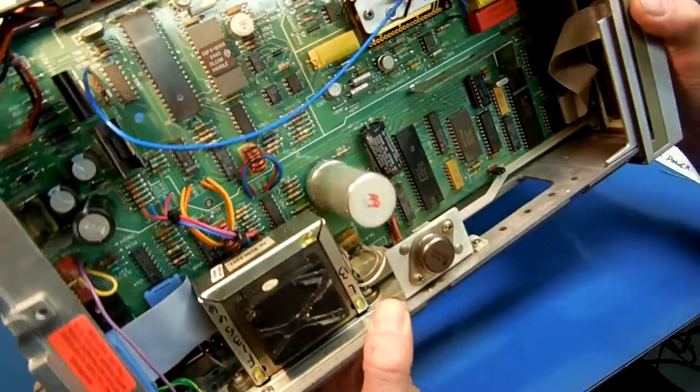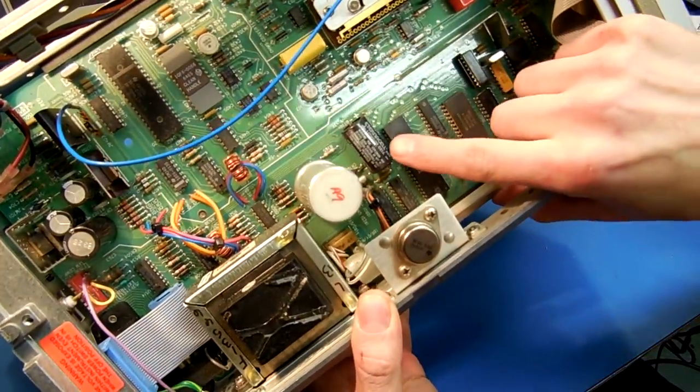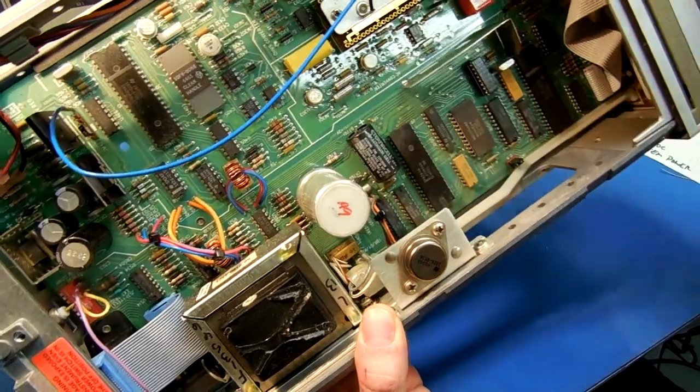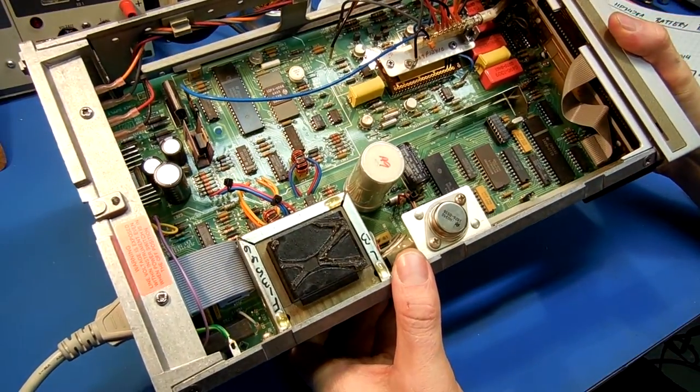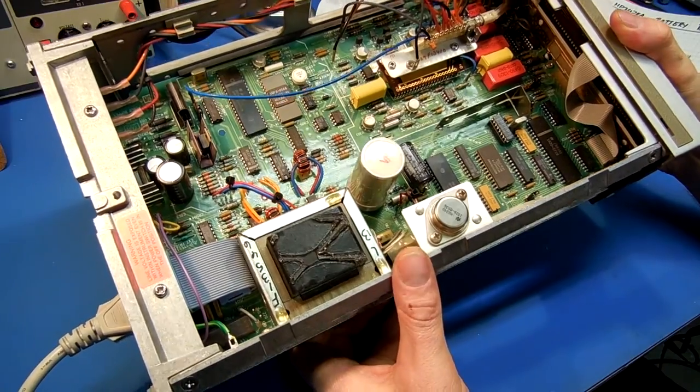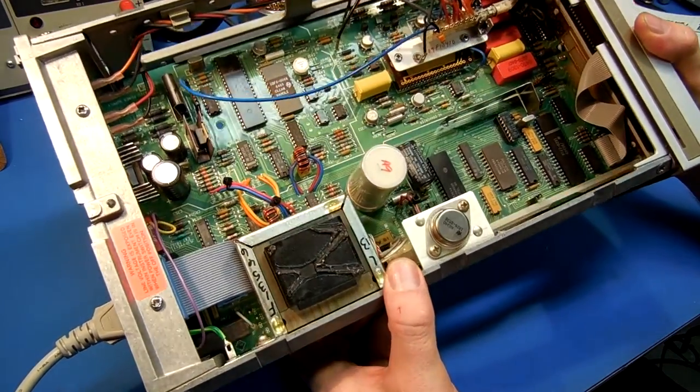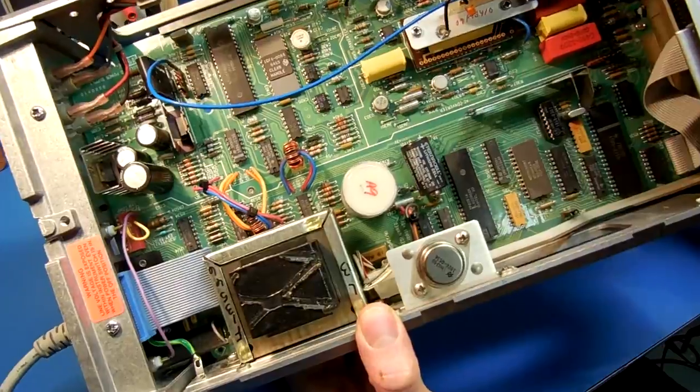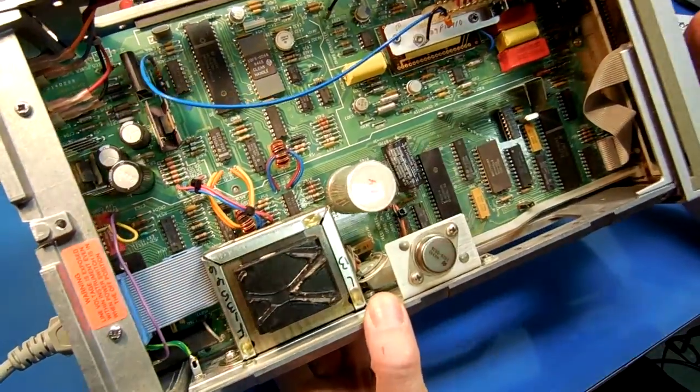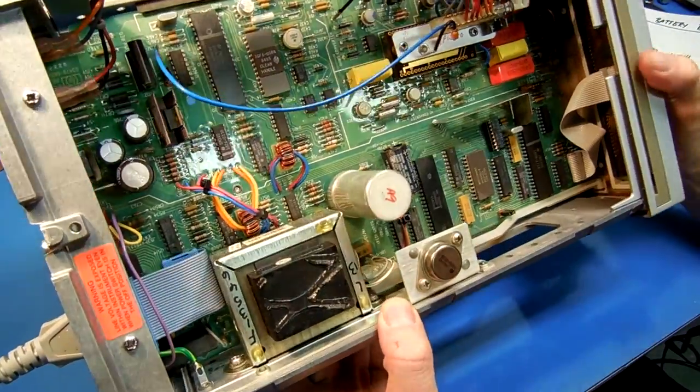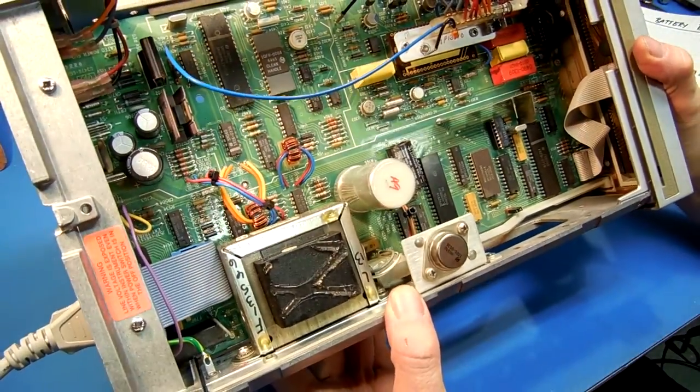This particular meter uses a 3 volt lithium battery to hold the calibration constants in a 5101 CMOS static ram. Most of these units are approaching 20 years old, so it's about time to replace the original lithium battery.